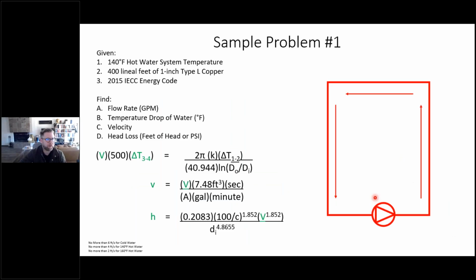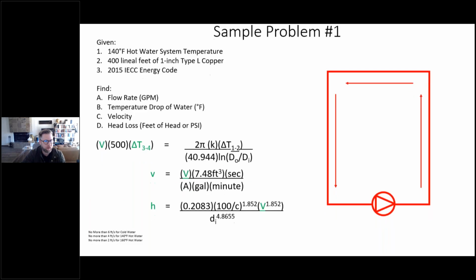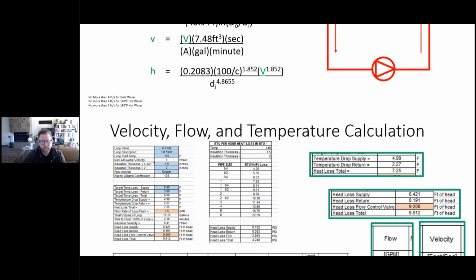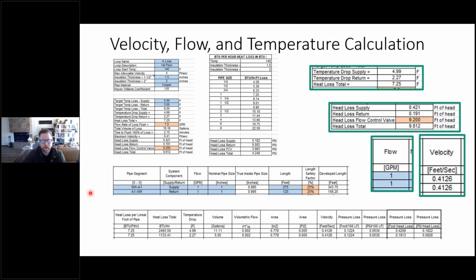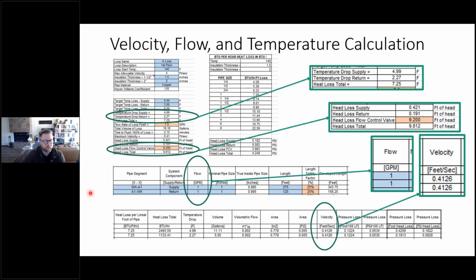So if we looked at a sample problem here, let's say assume a 140 degree Fahrenheit hot water system temperature, 400 lineal feet of 1-inch type L copper, and we'll assume the 2015 IECC Energy Code. If we wanted to find our flow rate, our temperature drop, our velocity, head loss of water, with, in essence, the 4 equations that we had, or 4 equations with 5 variables, depending on how you look at it. We could create a calculator, which we did as part of that ASPE Legionella Design Guide, going through consecutive iterations using those equations. And here's just kind of pointing out where those equations are.